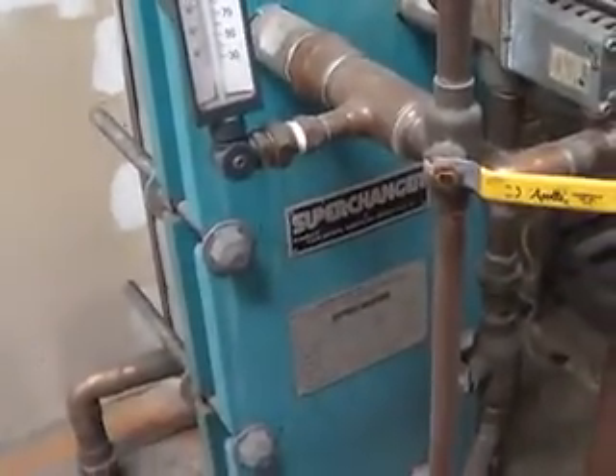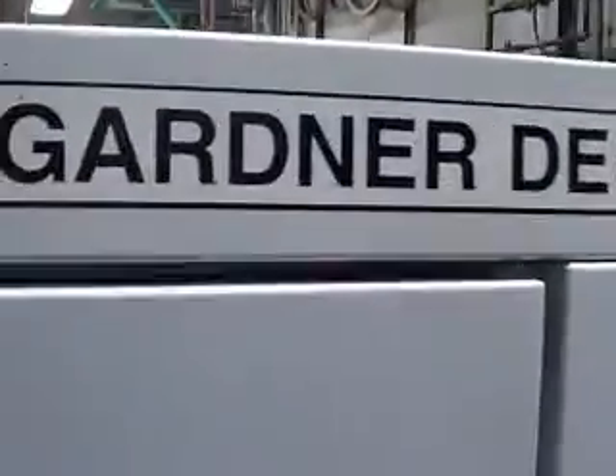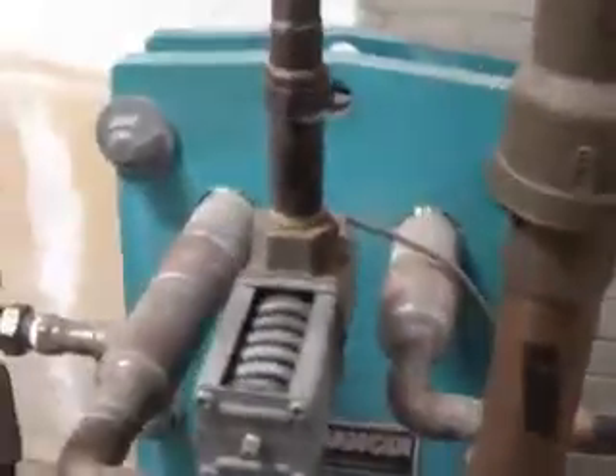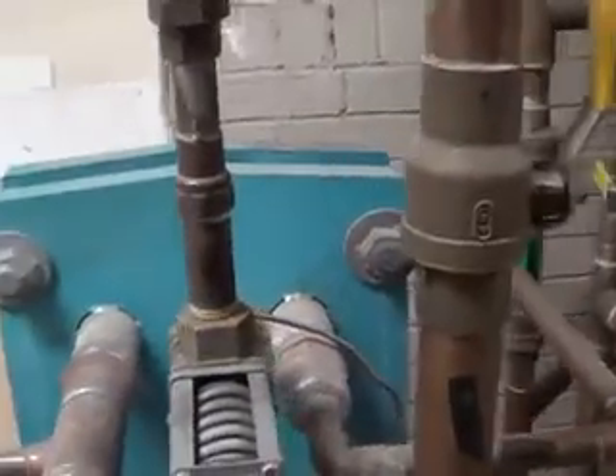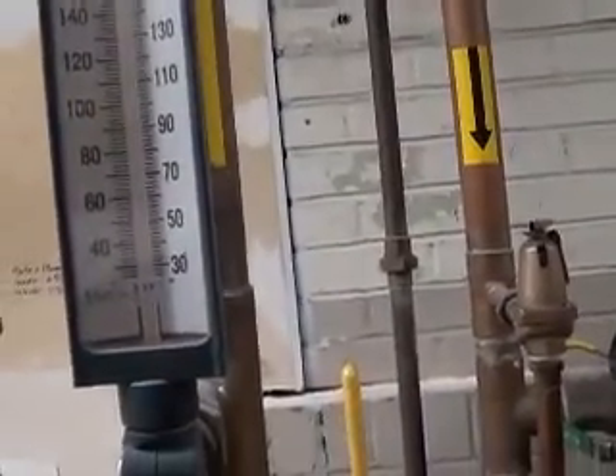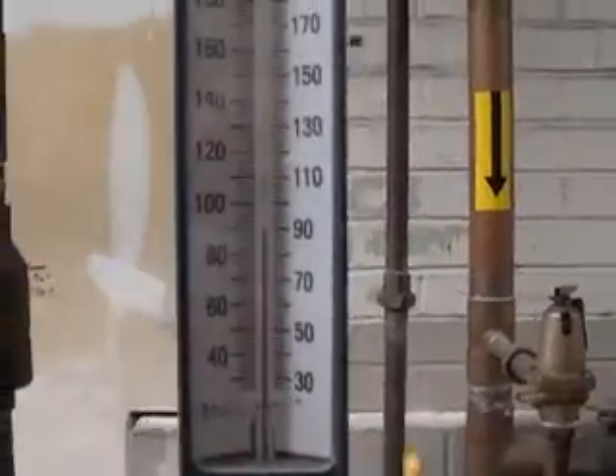Now these are water-cooled compressors, and the heat exchanger to cool it. There's the motor, the compressors in the front. There's the cooling heat exchanger. This is the pump that is circulating that water through this heat exchanger. I've got chilled water going in from my chillers, and I'm cooling that water down. This says 90 degrees. That's right on the button. Gonna look in the reservoir. Everything looks normal. Pump is on. Water flow is there. Switches are in the proper spot.